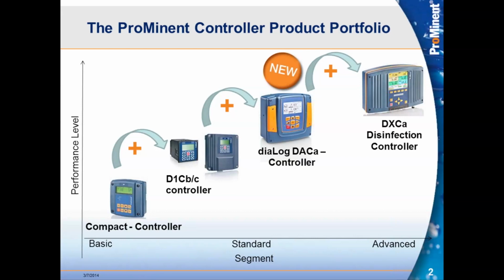You see the compact controller is at the bottom left there. It is our most basic controller. We do have an analyzer as well that would be maybe one step below that, our DMTA, and that is just a loop-powered transmitter, just a display, if you will. We can use that device also in place of a signal converter. So if you have a pH or an ORP sensor remote, but you want a local display, you can have the display right where the sensor is located, or very close to it. You could use that DMT and then transmit the output of that device back to either one of our controllers or a DCS SCADA system that might be supplying the voltage to them.